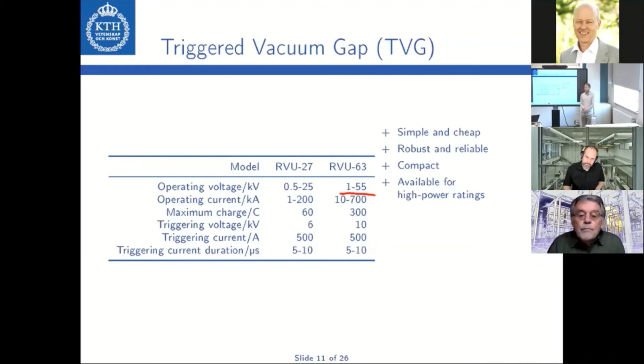During this interruption process, one can modularize the breaker, as I've shown on one of the previous slides. These boxes in the energy absorption path would each be an arrestor. So during the energy absorption process, the arrestor would define the voltage across each triggered vacuum gap in this case, similar to the conventional current injection DCCBs.